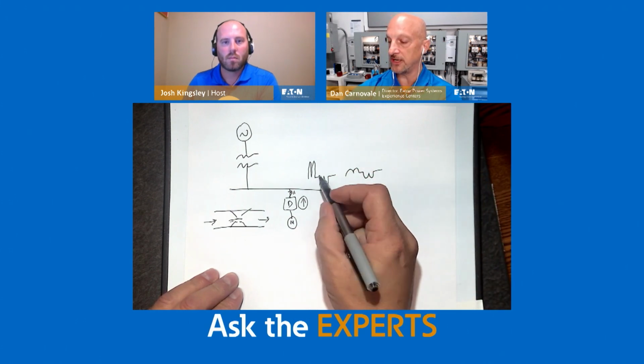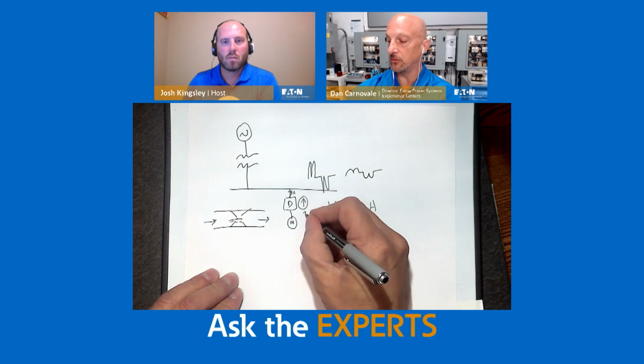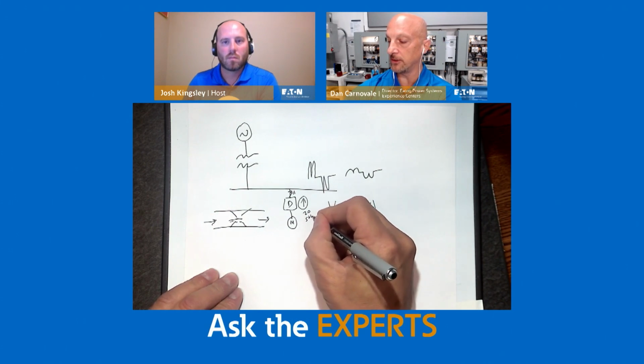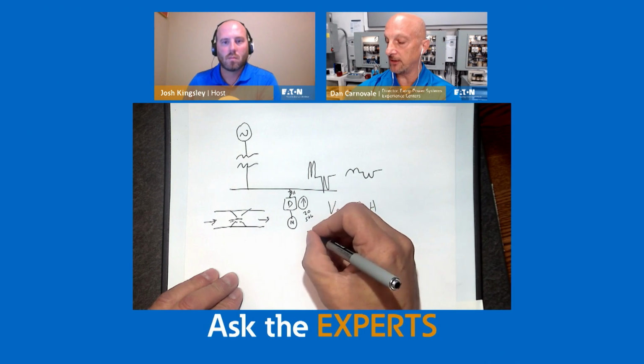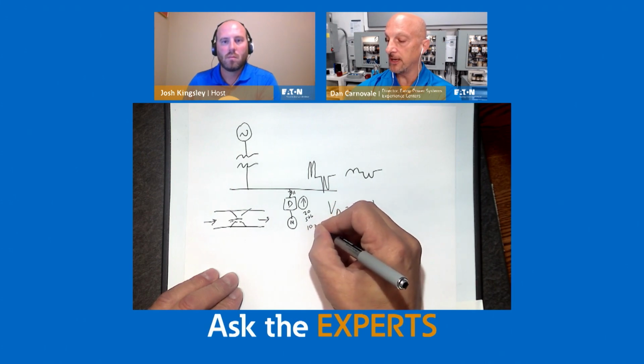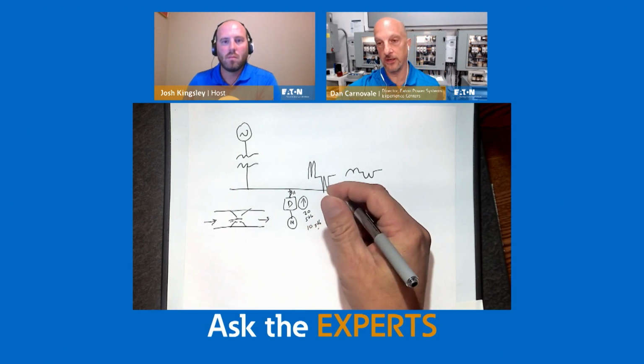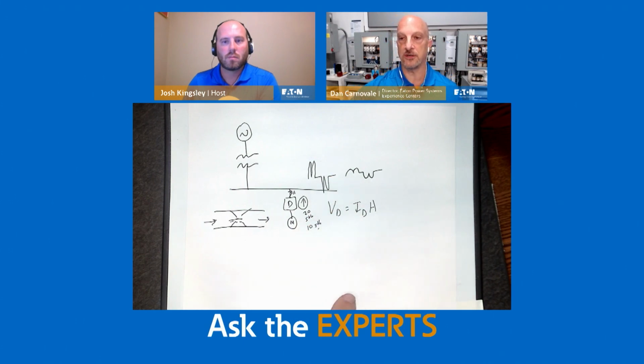So if in the first case we didn't have a reactor, we had 20 amps of, say, fifth harmonic current, in the second case we might have 10 amps of fifth harmonic current. And that is probably the least expensive version of things. Our drives, our DG1s, for example, and our other variable frequency drives have DC chokes built right in, and 5% is kind of the right number for that.